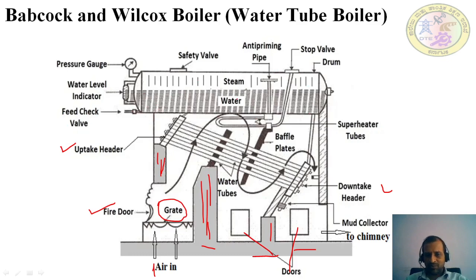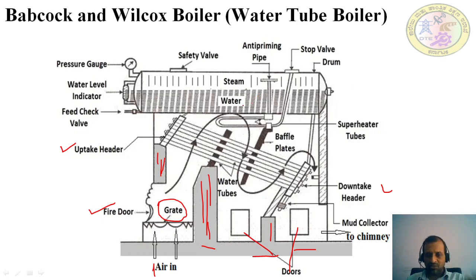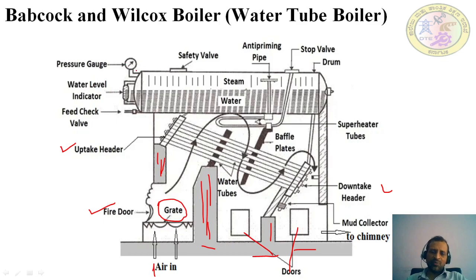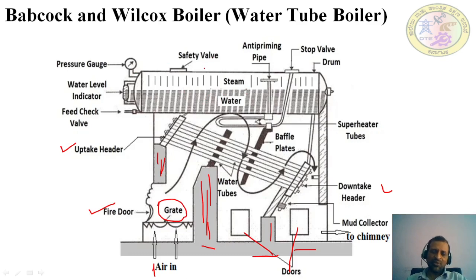When water is fed through the feed check valve, it enters the drum, where both water and steam are stored. The steam is stored in the upper portion and water in the bottom portion because of density difference. The water level indicator shows how much water is in the boiler, and the pressure gauge shows how much pressure is there in the boiler, based on which you can operate it.